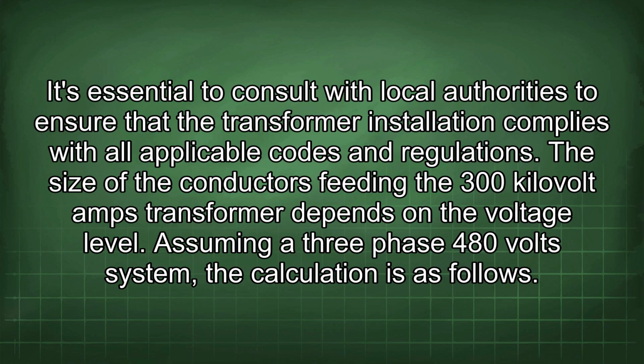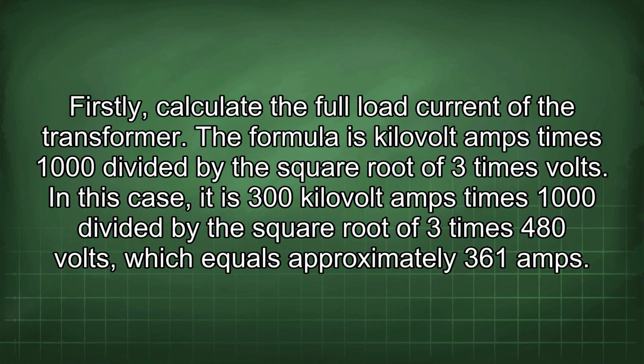The size of the conductors feeding the 300 kVA transformer depends on the voltage level. Assuming a three-phase 480 volt system, the calculation is as follows. Firstly, calculate the full load current of the transformer. The formula is kilovolt amps times 1000 divided by the square root of 3 times volts. In this case, it is 300 kilovolt amps times 1000 divided by the square root of 3 times 480 volts, which equals approximately 361 amps.